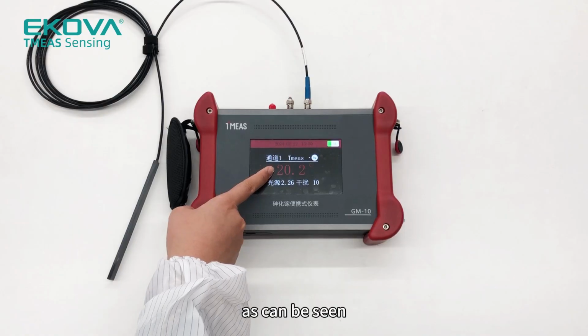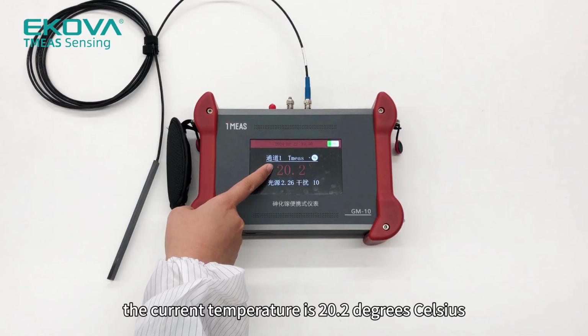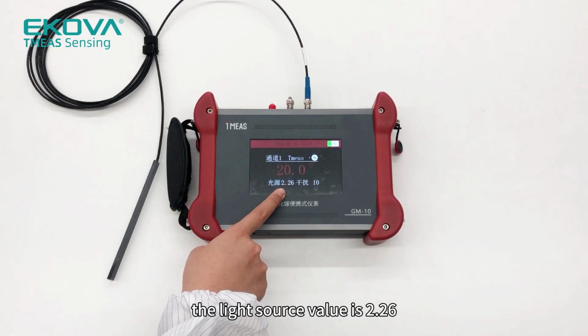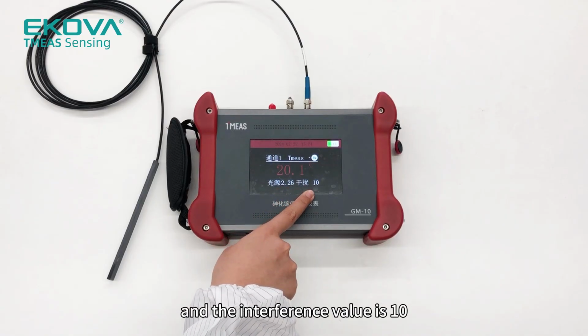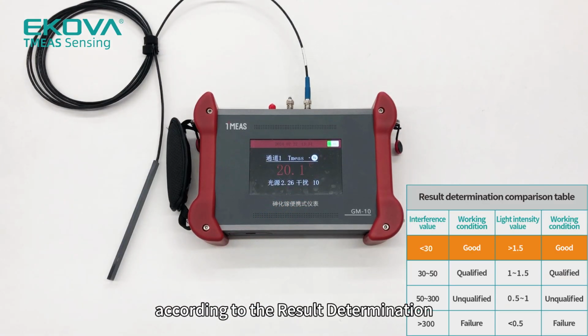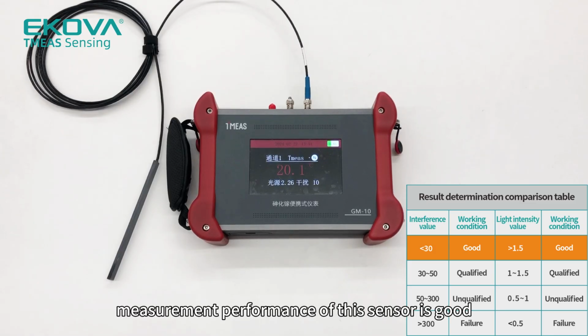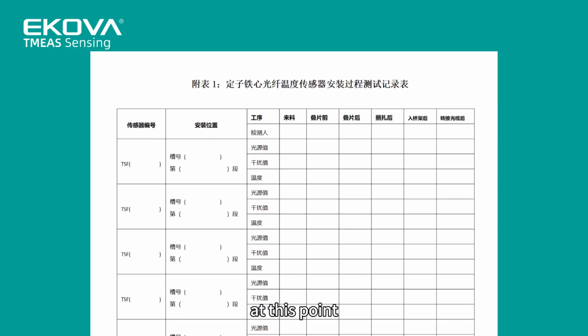As can be seen, the current temperature is 20.2 degrees Celsius. The light source value is 2.26, and the interference value is 10. According to the result determination comparison value table, it can be concluded that the temperature measurement performance of the sensor is good. At this point, we need to record the measured values on the corresponding installation process test record table so that the subsequent process can judge whether the previous process operation is normal.